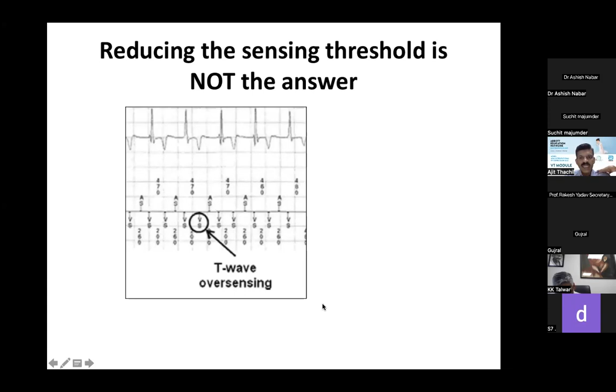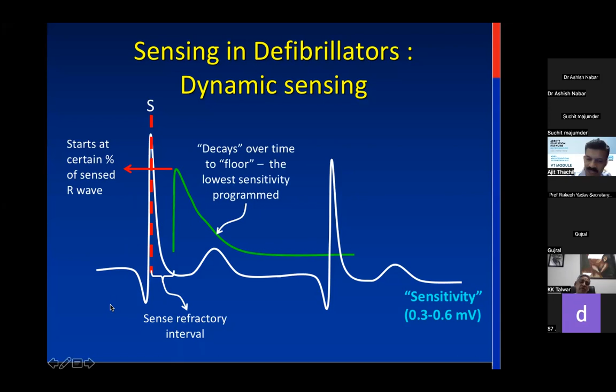So the idea is dynamic sensing. For example, we have this QRS complex. The sensitivity starts at a certain percentage of the sensed R wave. It will vary from manufacturer to manufacturer, about 50 to 75%. And then there's a refractory interval. You do not sense 100 milliseconds after a V-sense event and 150 milliseconds after a V-pace event, because otherwise you might sense the same event again. After the refractory interval, you start sensing at a particular percentage of the sensed R wave. This takes care of the variations in RR intervals and in the R wave height.